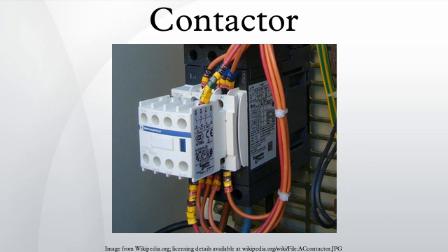Contactors for medium voltage motors are rated by voltage and current capacity. Auxiliary contacts of contactors are used in control circuits and are rated with NEMA contact ratings for the pilot circuit duty required. Normally these contacts are not used in motor circuits. The nomenclature is a letter followed by a 3-digit number. The letter designates the current rating of the contacts and the current type, and the number designates the maximum voltage design values.